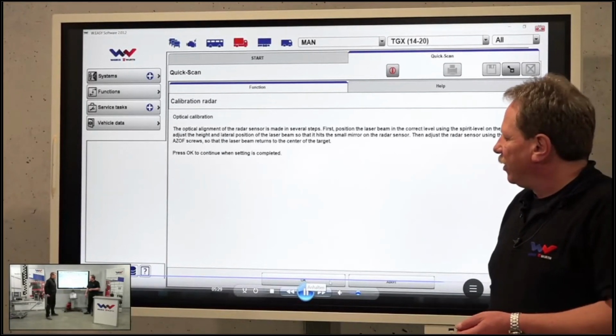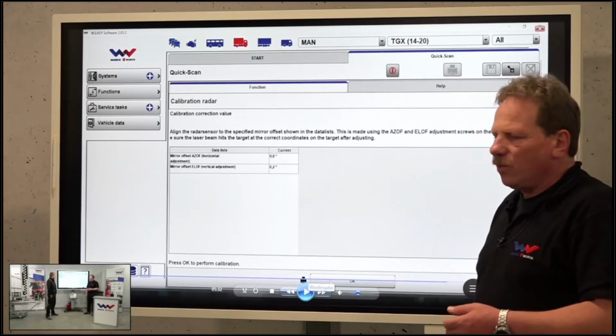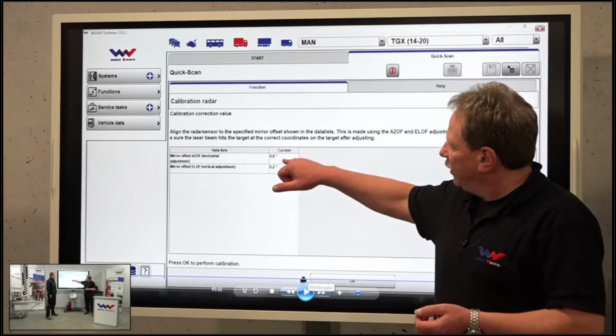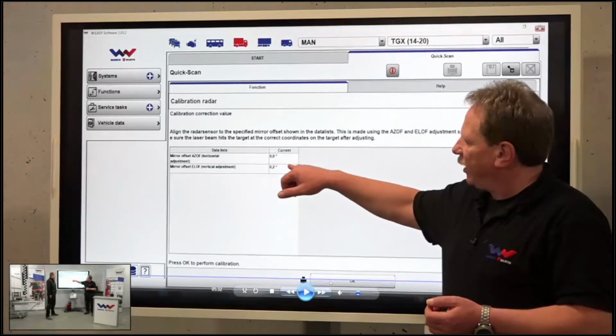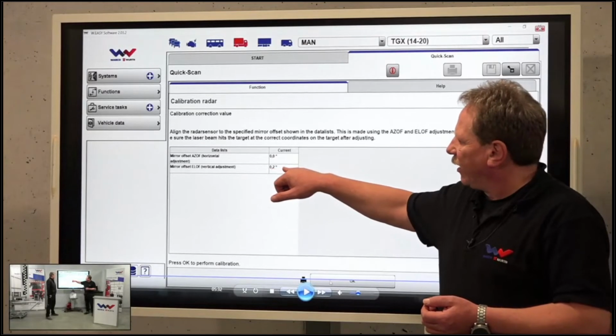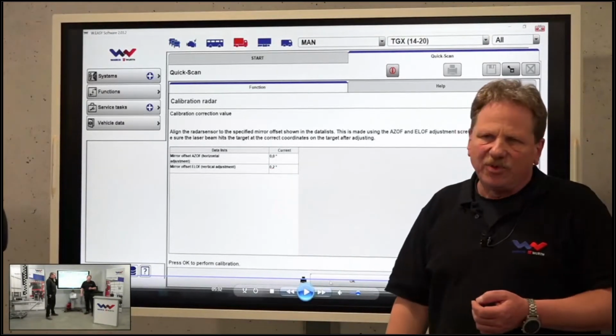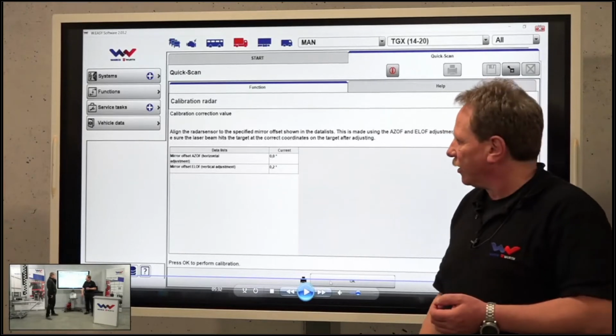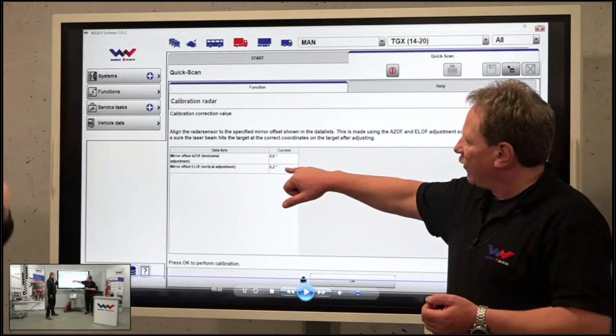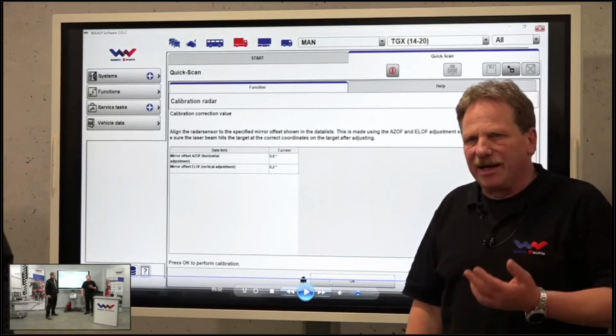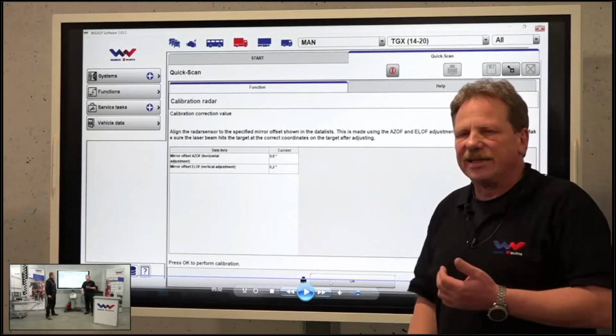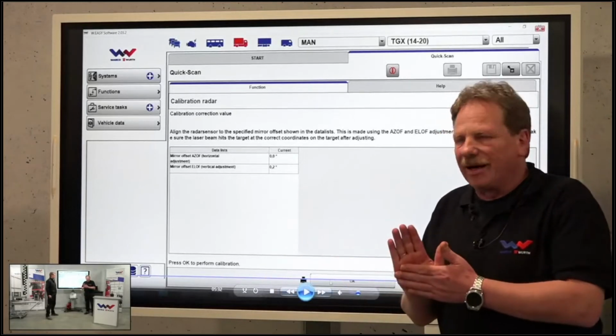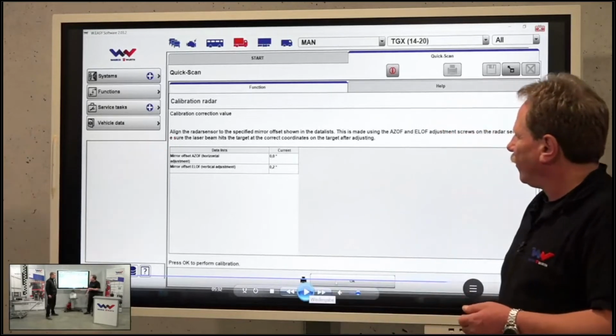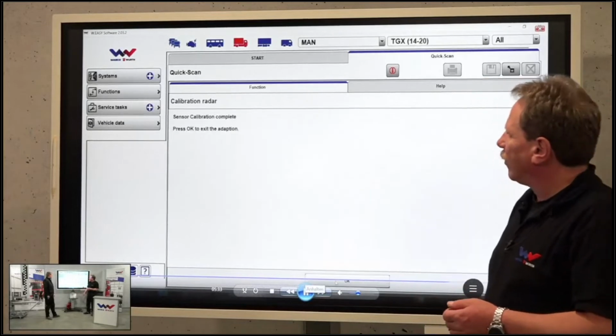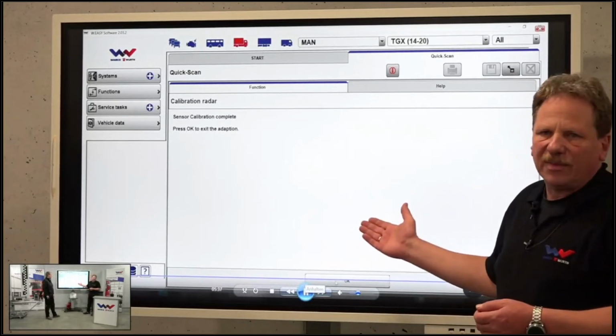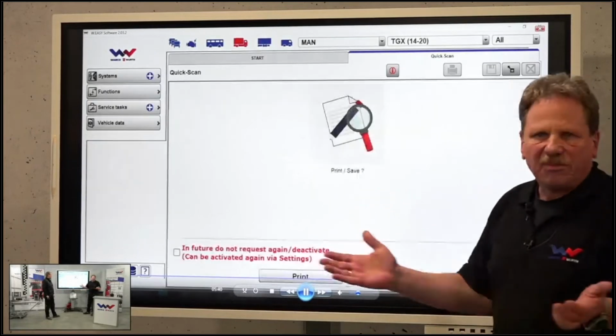In the first step, we read out the calibration data, which is stored in the radar head. These are the informations we need. The AZOF, the horizontal adjustment, and the ELOF, the vertical adjustment, so the azimuth calibration and the elevation calibration. One is at 0 degree, the other at 0.2 degree. This is the number which I have to compare, which we will see in the next step, on the gauge of the target. Yeah, so we have to memorize those numbers, and you will see in the next step. So from the diagnostic system view, calibration is completed.